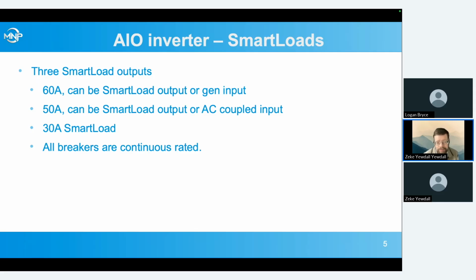All of these amperage ratings, both the 100 amp pass through and the 60 amp, 50 amp, and 30 amp on the smart loads, are continuous ratings. They're not like typical AC breakers where you're looking at 80% of the amperage rating for continuous use. These breakers are all continuous rated.